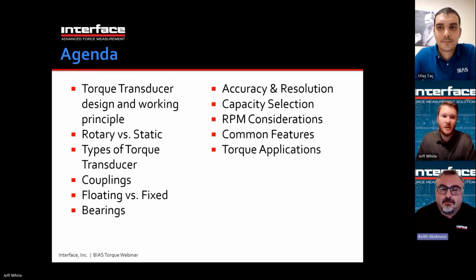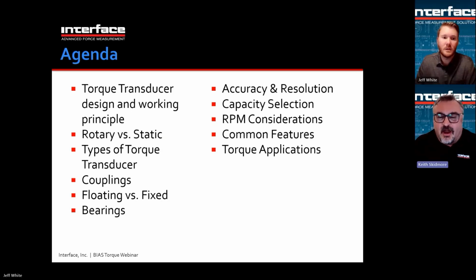Well, today we will be talking about torque transducers, design and working principles, basically how they work and what the technology is behind them. There are different types of torque sensors, ones that rotate and ones that do not. We call the ones that do not rotate static or reaction torque sensors. There are also different styles or types of torque sensors: flange style, shaft style, specialty types. Couplings are the devices that are used to attach torque sensors to the other components in the test string. For mounting torque sensors, they can either float or be fixed mounted. We're going to talk about the difference and pros and cons of each approach.